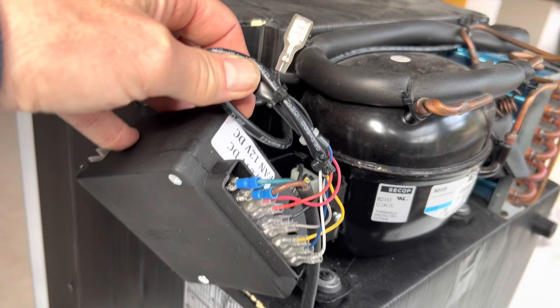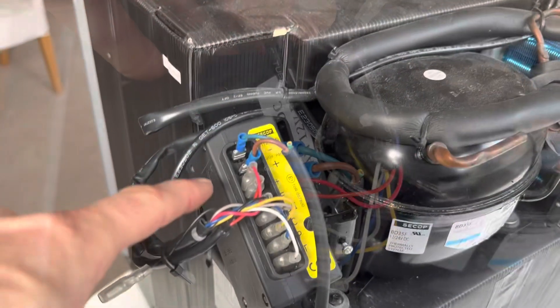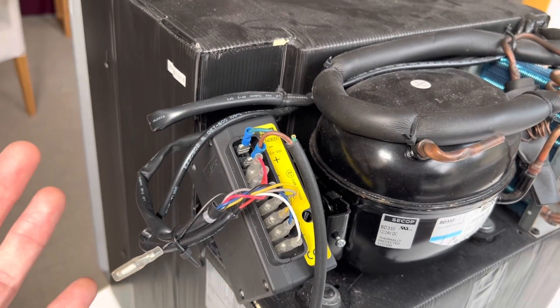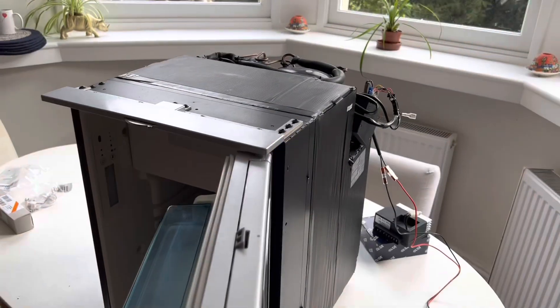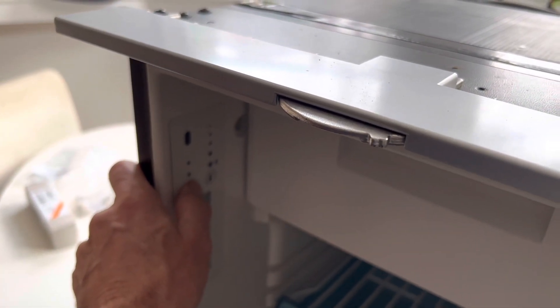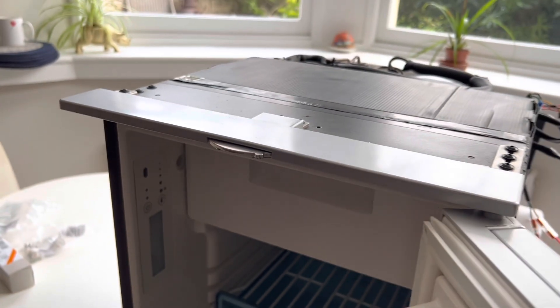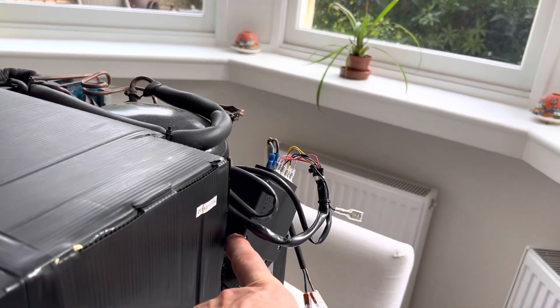I'm filming this so that when I send the company a link to this video, they'll know I've hooked up their controller correctly. I've just hooked up the faulty SECOP control unit — this is to show you the symptoms of a faulty control unit. With the power turned on, the first thing to notice is that the fridge does not automatically come on. Holding the on/off button should make it spring to life, but nothing happens. If your fridge is as dead as a doornail, there's a good chance your control unit is faulty.